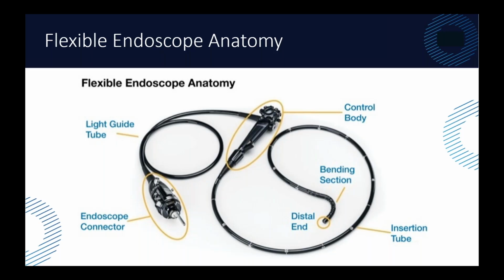And after the insertion tube, we have the articulation, in this case what they call the control body. This allows them to rotate, and there are wires inside that actually pull the bending rubber and the distal tip into different positions so they can manipulate where the probe's going, get a better image, and so on. And then we've got the cable going out to the light guide on the endoscope. For a TE probe, it's just a connection going to the ultrasound machine. Those are pretty similar.